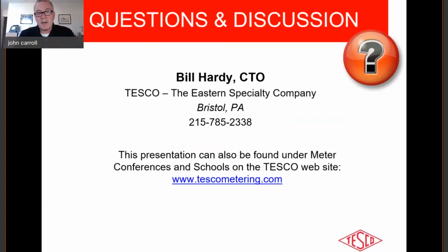Yeah, certainly in the experience that I went through with Jeff, particularly at CDFA, and his colleague down in Southern California, timing was a concern. With the amount of EV installations, type approval installations, similar to a gas station which may have 15, 20 pumps on it, each one has to be tested. So timing is an issue for them. They want something quick and easy that doesn't take a lot of training. We went through some basic training with them, and they were pretty delighted that the instrument will take care of the HB44 test for you. That's something they really appreciated, because it will save them quite a bit of time and deploying so many people to do this.